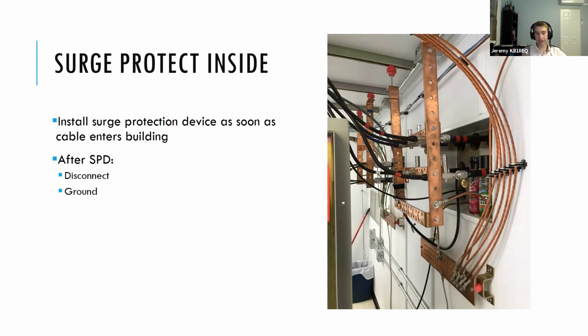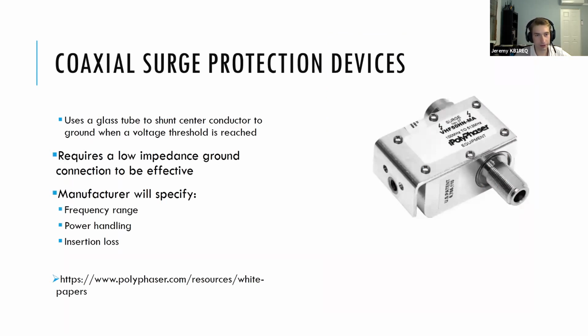Why you need to ground, even if you have a surge protector and leave it disconnected, is something we'll talk about as we go into a little detail on coaxial surge protectors. The basic way these work is that it uses a glass tube inside the SPD that shunts the center conductor to ground when a certain voltage threshold is reached. Essentially, when the voltage gets too high, this switches so that the center conductor in the cable is connected with ground.